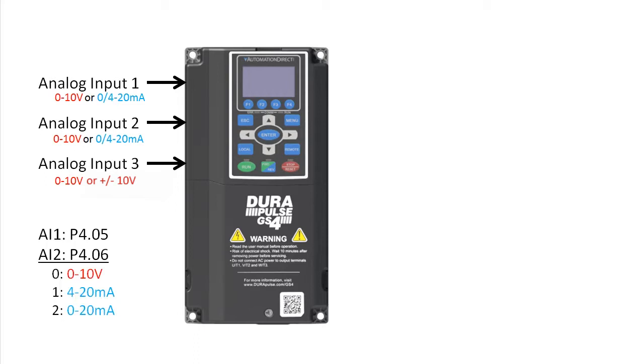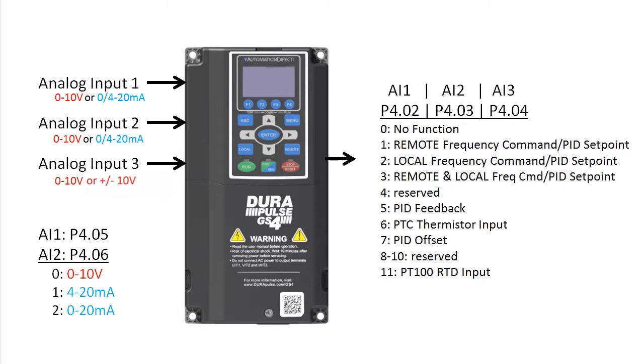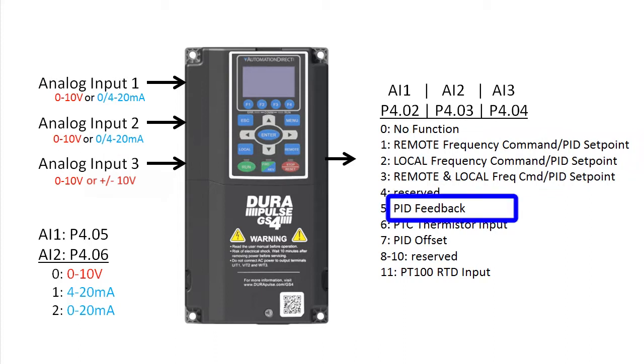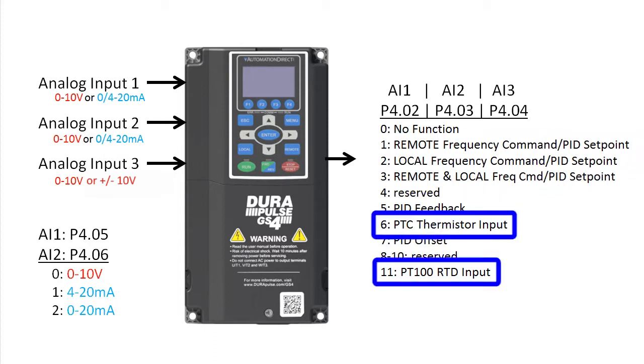The cool thing about these analog inputs is any of them can be used for any of these functions. You can use them to control the frequency of the drive, as a PID set point, feedback or offset, or even use them to monitor the temperature of the drive and automatically generate warnings or faults.